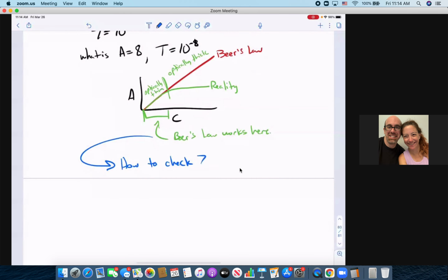So how to check? Dilute. You can just do it once even, right? Absorbance is generally not linear above an absorbance of 2, right? That's 99% being absorbed, right? That's 1% transmission. So you've got almost everything gone at that point. Think about it this way.